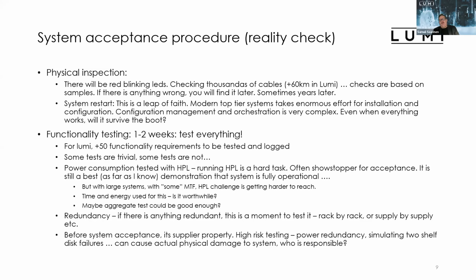Actually, the reality check: during the physical inspection, there will be these red blinking LEDs. Also, checking thousands of cables is not realistic. So basically, checks are based on samples. You cannot open every single blade and check whether there's dust. But the problem is that if there's anything wrong, for example, with the network, we will find it later. Sometimes you can find some miscabling years later and find out that, okay, that was the reason for this problem.